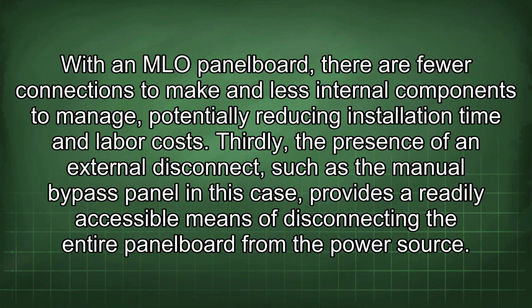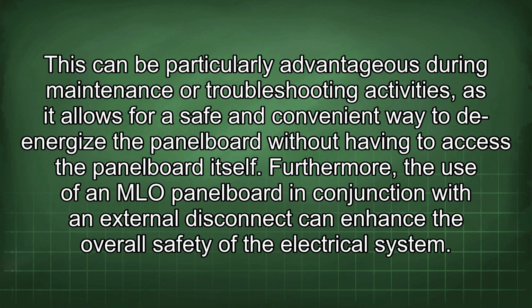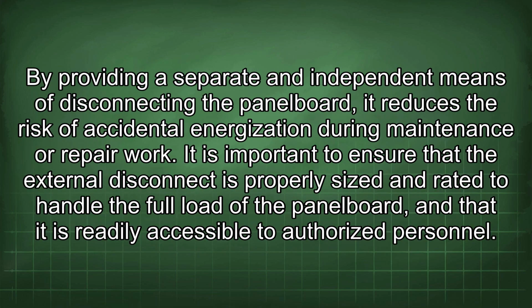Thirdly, the presence of an external disconnect, such as the manual bypass panel in this case, provides a readily accessible means of disconnecting the entire panel board from the power source. This can be particularly advantageous during maintenance or troubleshooting activities, as it allows for a safe and convenient way to de-energize the panel board without having to access the panel board itself. Furthermore, the use of an MLO panel board in conjunction with an external disconnect can enhance the overall safety of the electrical system. By providing a separate and independent means of disconnecting the panel board, it reduces the risk of accidental energization during maintenance or repair work. It is important to ensure that the external disconnect is properly sized and rated to handle the full load of the panel board, and that it is readily accessible to authorized personnel.